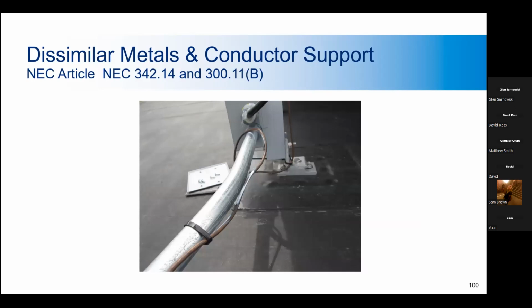Here we have the raceway being used to support a conductor, which is the ground wire. Code is limited on what conductors you can have supported on the outside of a raceway. You can also see the galvanic reaction between the copper conductor and the coating of the raceway. The ground wire will eventually corrode and deteriorate over time, and that'll cause a failure in the grounding system. Basically, the only thing that's allowed to be attached to the outside of conduit is something like data wires, which are typically low voltage.